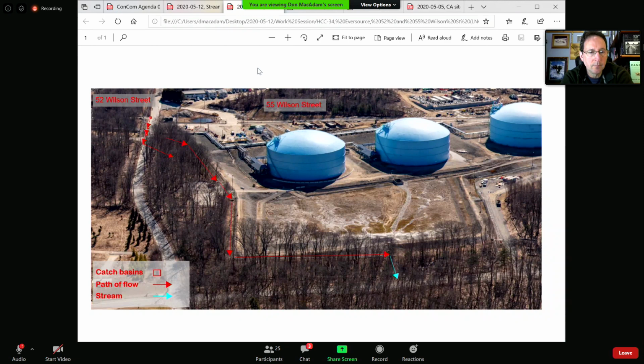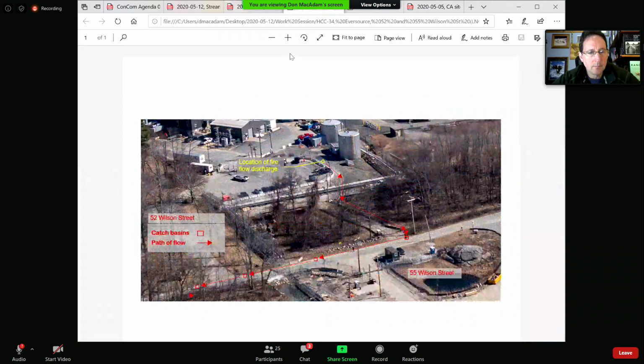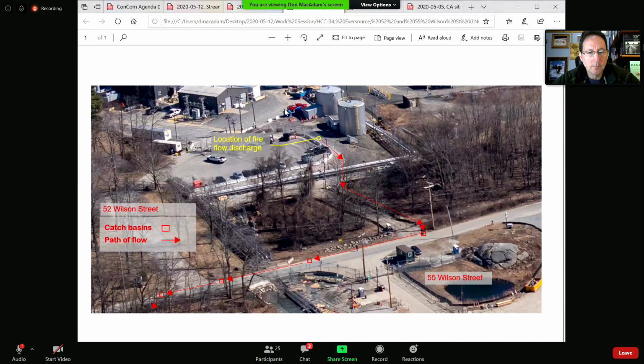So what took place that day, there was some fire pump testing that had been planned by the operations group. We had a fire pump contractor on site to do some flow testing. What they had done is set up a manifold, and they were testing both our diesel engine driven fire pump and also our electric driven fire pump. Really, it's a 10 to 15 minute test, but it's a very high flow test. I think we're putting out about 2,000 to 2,500 GPMs of city water through each of those pumps to test their performance after some maintenance that had just been done.